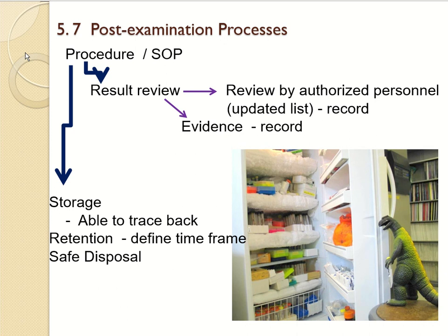Clause 5.7 is about the post-examination process. So the lab shall have a procedure and SOP and should follow it for result review, meaning that the review should be done by authorized personnel, and there should be a record and an updated list of the authorized personnel involved in the result reviewing, and evidence of result review. Usually it is recorded in the result report. There should also be a procedure and SOP for the storage of the patient sample after the test is done. The patient sample should be traceable, the lab should determine how long the sample needs to be kept, and should have a procedure on how to dispose of the patient specimen in a safe method.